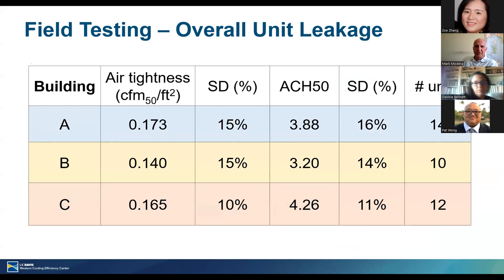Here are the leakage results in more detail. In building A — affordable housing with a 0.3 CFM target — that's where it landed. Building B had no tightness target but was modular construction. Building C had a tightness target of 0.23 and clearly beat that. This is the standard deviation I referred to earlier. We also expressed results in air changes at 50 Pascals, and those don't exactly scale because the surface-to-volume ratio is not the same for all units.